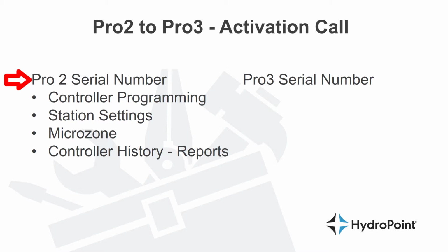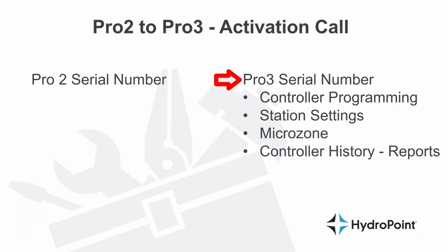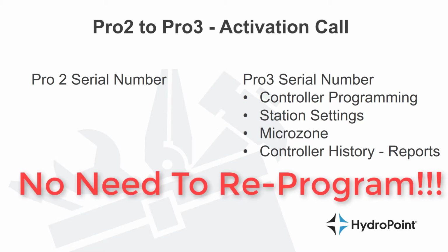The old Pro2 serial number has all of the controller's programming, including the station settings and microzone location information, as well as all of the controller history about runtimes and settings changes. When you activate this controller, you'll tie the Pro2 serial number to the Pro3 serial number, which allows us to carry over all of that information. This is a blessing because not only do you not need to reprogram everything, but the management history stays in place.